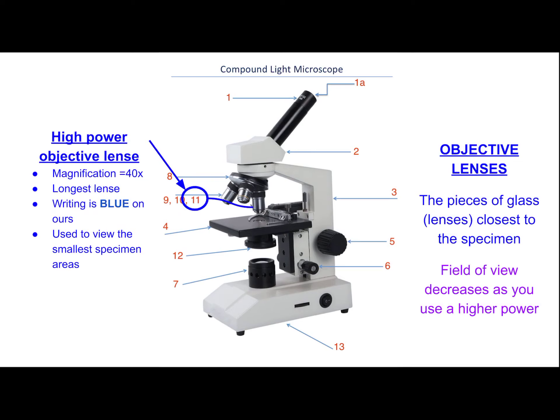Number 12, underneath the stage, is the diaphragm. The diaphragm adjusts the amount of light that passes through the specimen. It's sometimes used along with a condenser — our scopes do have a condenser. The condenser narrows or widens the beam of light passing through. If you have a dark or thick specimen, widen the beam so more light gets through. If you have a very thin specimen, narrow the light so the brightness doesn't drown out the image. Adjusting this can help you see the image more clearly.